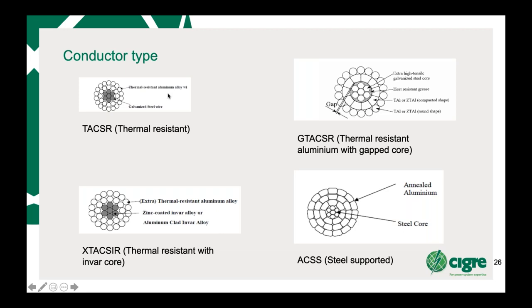You can get a thermal resistant conductor. You can get a thermal resistant conductor with an Invar core. Invar means it's invariable to temperature. And you get an extra thermal resistant aluminium alloy, which is then around 200 degrees C. Or you could use a gap conductor, which will reduce the knee point of the particular conductor. And you can then use a TAL or ZTAL, depending on the particular type of aluminium that you wish to use.